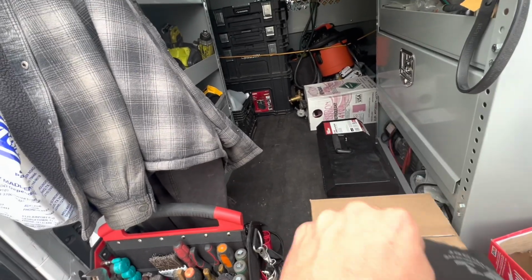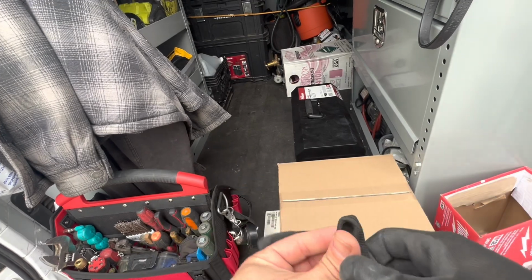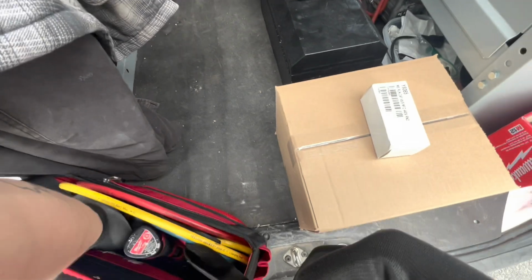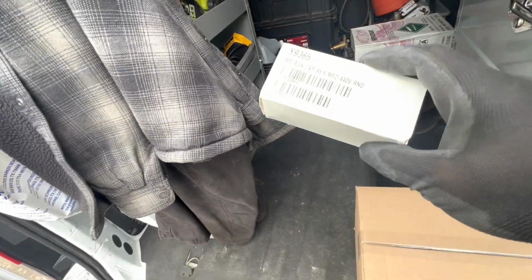But I'm pretty sure if I leave that fan like that, it's going to quit on them eventually, and they're going to call back and bust my butt for it. So I prefer to replace it and get done with it. So got a new capacitor here.